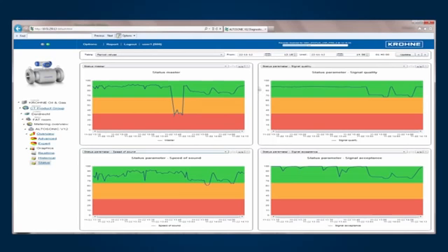And if I look in the other graphs, for example the signal quality, the signal acceptance and the speed of sound, I cannot really explain this dip. Besides this dip, there's a few other things I see. I see the signal quality here dropping, going up, dropping and going up again. I see signal acceptance dropping and speed of sound going up and down. So something happened to this meter.